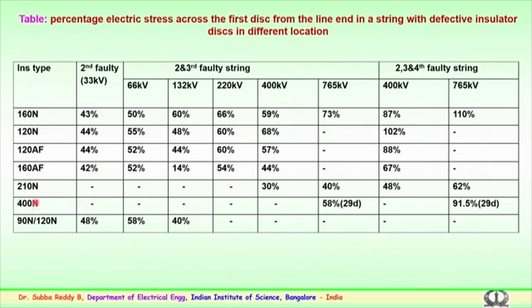These discs are normally used for HVAC and DC lines, and for the case where the second disc is faulty, the voltage levels are also given here. For only the second disc being faulty, these are the stress values which increase across the first disc. The second and third discs are considered faulty for various voltage levels up to 765 kV. You can see how the percentage stress increases across the first disc for various voltages. For a typical 765 kV, you can see a 73% increase in the stress across the first disc. Similarly, this is for 29 discs of a 400 kilonewton insulator, where 58% of the stress is increased across the first disc. For 3 insulators faulted, that is the second, third and fourth from the line end, these are the stress values that the first disc insulator sees.